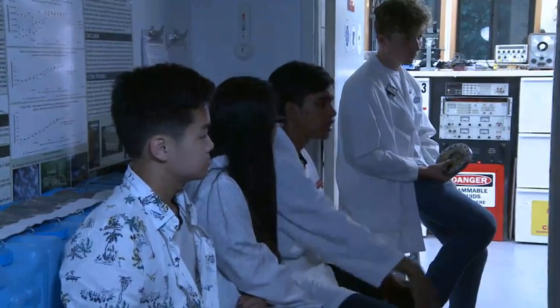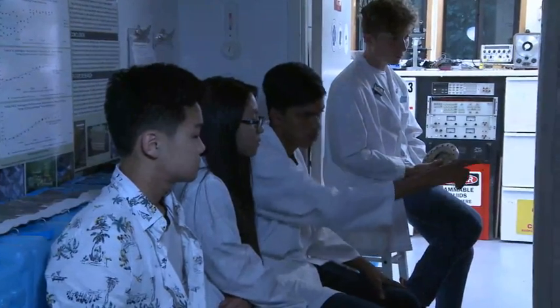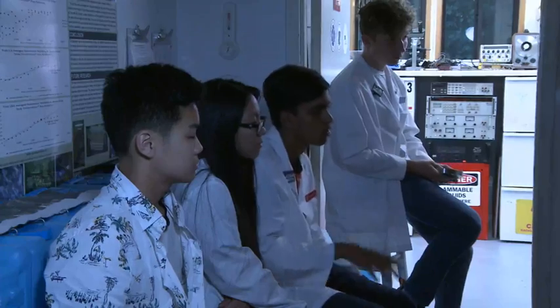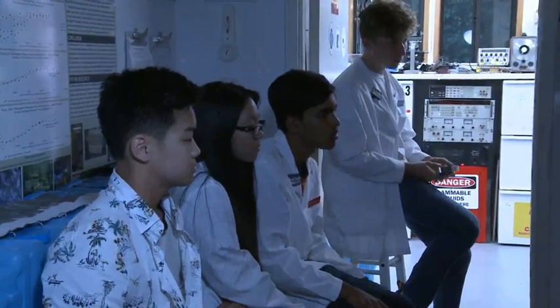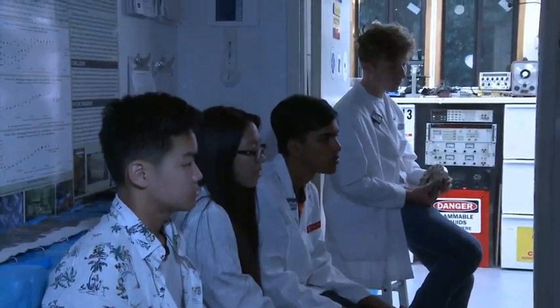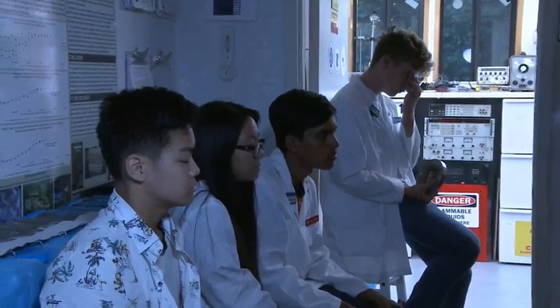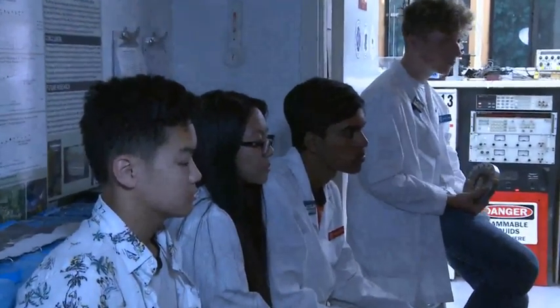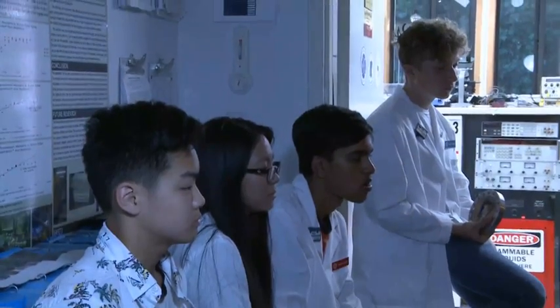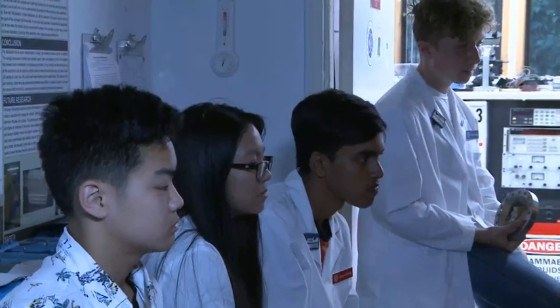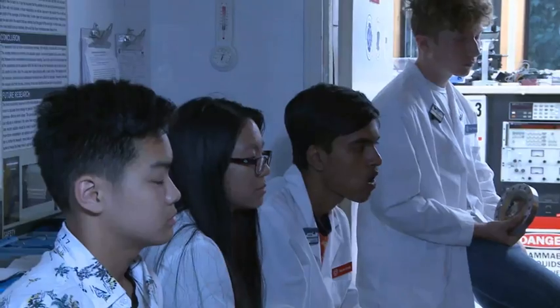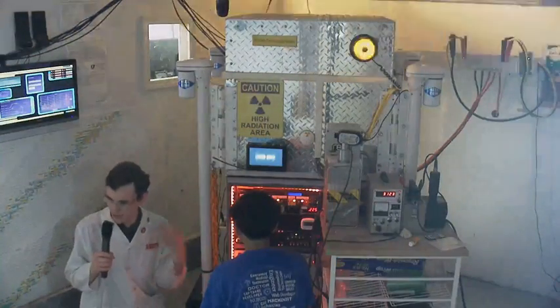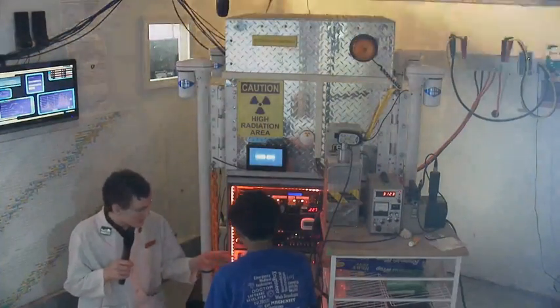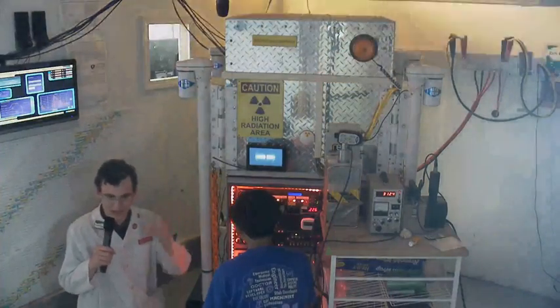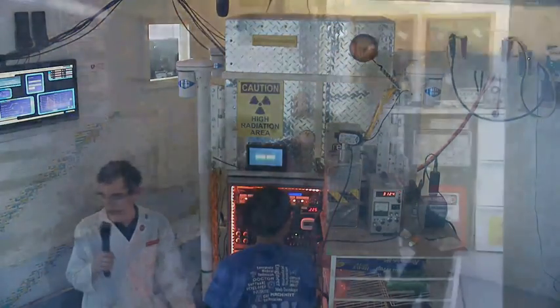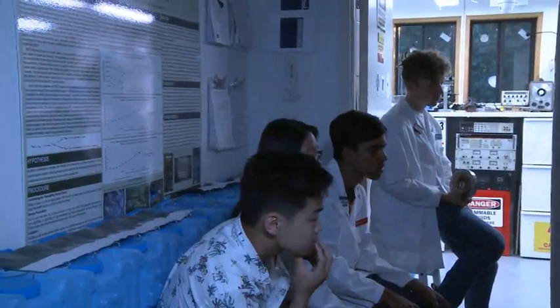Yeah. So what do the 4 dials do? Like what's the 1, 2, 3, 4? This reactor is configured to supply multiple gases simultaneously to the reactor vessel. Our controller can control 4 of those mass flow controllers at once. I'm only using controller number 2 right now because I'm only flowing deuterium gas into the vessel. In reality, I only have 3 working controllers on the instrument right now, and only one of them is even plumbed into something. So if I opened one of the other ones up, I'd just be letting air into it. You can do stuff with that, but it doesn't produce fusion.